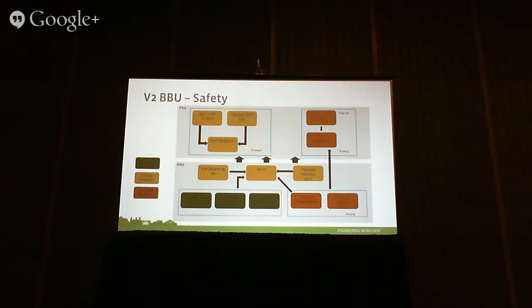On top of that, we have strictly analog signals between BBU and power supply. For that, we have internal voltage sense directly as the BBU sees it, connected directly from the BBU to the power supply. We also have temperature sensors set at higher limits than the internal ones to the BBU, connected directly to the converters of the power supply, and they can stop the power supply from using the BBU quickly.